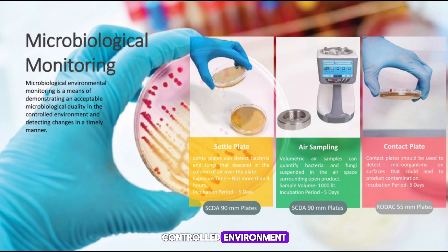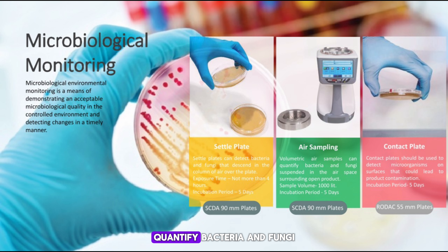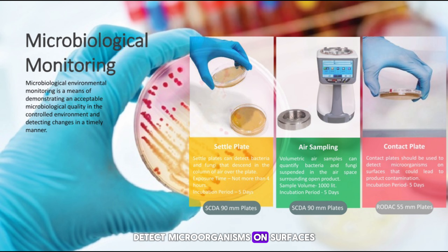Microbiological Monitoring and Classification — Microbiological environmental monitoring demonstrates acceptable microbiological quality in the controlled environment and detects changes in a timely manner. Settle plates detect bacteria and fungi that descend in the column of air over the plate; exposure time not more than 4 hours, incubation period 5 days, using SCDA 90 mm plates. Air sampling: volumetric air samples quantify bacteria and fungi suspended in the airspace surrounding open product; sample volume should be 1000 liters, incubation period 5 days. Contact plates should be used to detect microorganisms on surfaces that could lead to product contamination; incubation period 5 days.